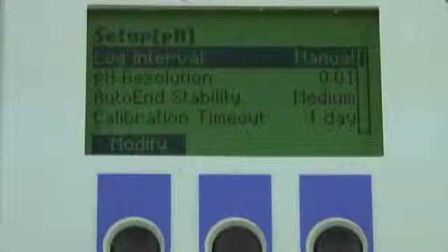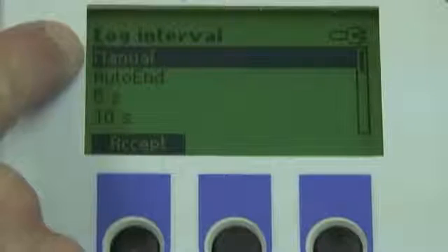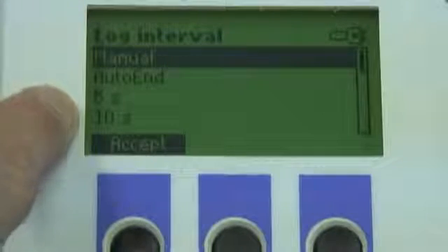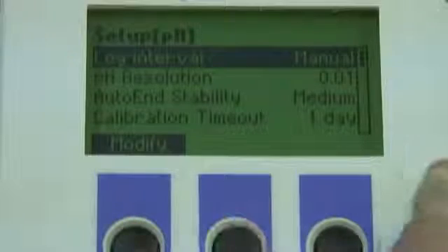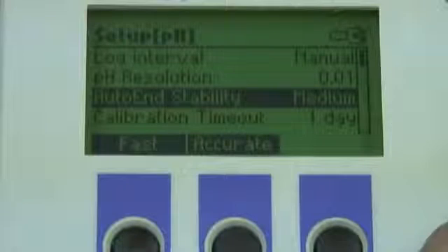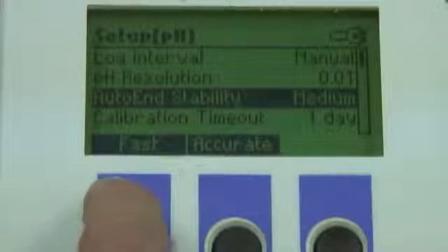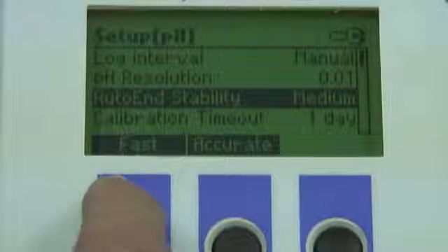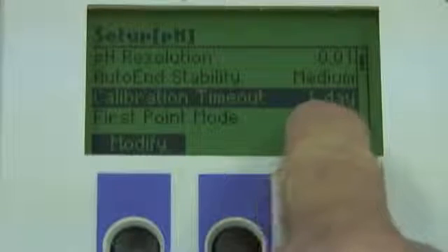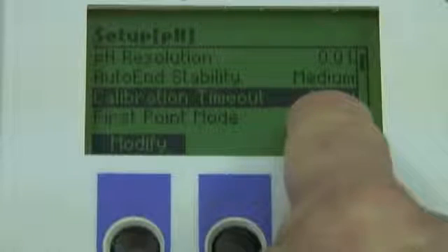and go into the setup features. Since I'm in the pH mode, let's look at its setup options. The first item we see is log interval. If I push the button, I can choose from either manual, auto end, or intervals from every 5 seconds up to 3 hours. Next is the pH resolution. I can choose from 0.1 to 0.001. Auto end stability. So if drift is not an issue, then I can choose to do it very fast, or if I need a very accurate reading, then I push the accurate button. Calibration timeout. So in this case, the meter is set to 1 day. Once 1 day hits, then the meter will tell us that it's time to calibrate our probe.